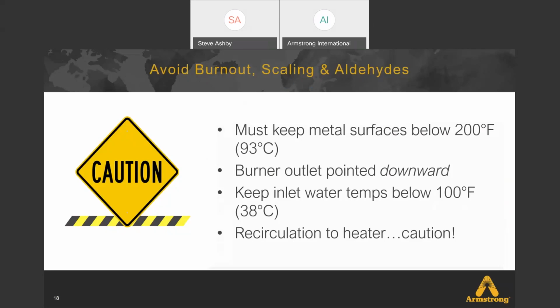So typically the leaving water from our heater into the bottle warmers is 120. That temperature comes back then recirculating at 80. So we still stay in a band of acceptance on your water temperatures. We're not coming into the heater over 100 degrees. Therefore, we're not heating the internal surfaces beyond the 200 degrees. So we avoid the scaling issue, and that is an acceptable application that works quite well in a recirculating manner.